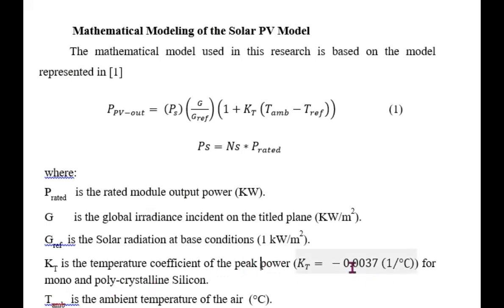This is equal to minus 0.0037 or 0.0034 depending on your type. This may be 37, 35, 37. This is the degradation temperature coefficient, per centigrade. Means, the power of that solar panel is degraded, with respect to per centigrade temperature increase, above the reference temperature.